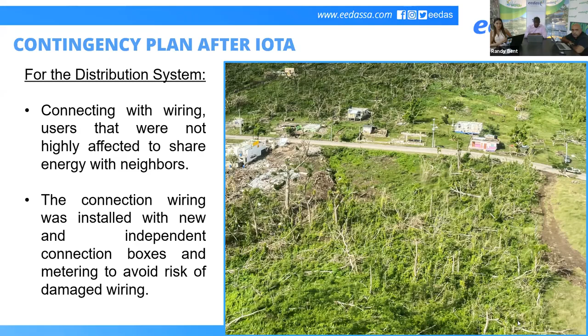For the users, after we recovered the medium tension line, we started slowly because the damage to the wiring system of the low voltage system was very high. We started to recover those users that had their installation in good condition. We deployed independent connection boxes and metering to avoid the risk of any damage inside the houses. And we recommended that people share the energy with their neighbors, so everybody can charge their equipment, or have some opportunity to keep freezers running or save food.